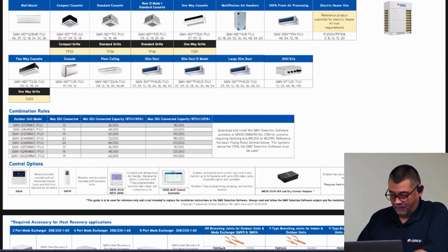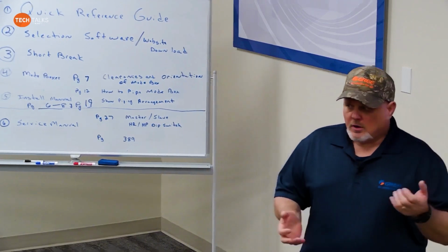Now, the other thing I want to point out too, Robert, is back to the max indoor units connected. Be careful what you guys are doing out there. A lot of people think with inverter-driven equipment, I don't have to do a load calc. Yes, you do. Just because you can zone every room doesn't mean you should zone every room. Be careful in making sure that you're getting the right unit for the application, the right size. I just talked about it in my last broadcast about MultiPRO. In what world do you put a 1-ton cassette in a 100 square foot room?